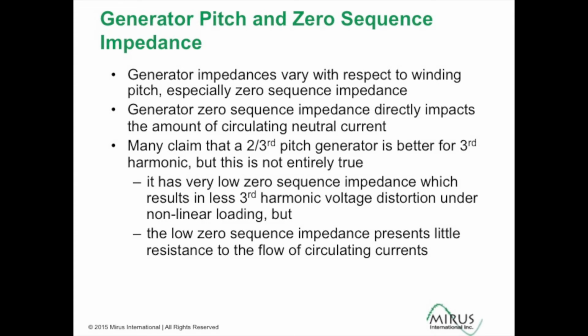The main reason for this is that, in addition to the level of voltage distortion that drives the circuit, a key parameter in how much circulating current will be present is the zero sequence impedance of the generators being paralleled. A 2/3 pitch generator has very low zero sequence impedance, and therefore will present little resistance to the flow of the circulating currents.